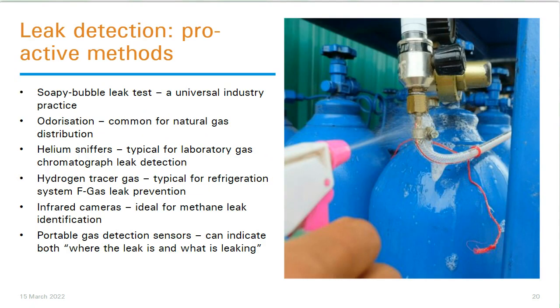What about proactive methods of identifying leaks? These are the kinds of things that you can do during a safety walk or during a regular routine maintenance operation. We can go out with a soapy bubble leak test, a universal practice, and check for leaks. Or we can use infrared cameras to look for IR-specific molecules such as methane. Or we can walk around the site with a portable gas detector, and if it's a multi-gas detector, it can perhaps tell us, number 1, if there's a leak, and number 2, which particular gas is leaking. So there are a number of appropriate techniques that we can use proactively to track down leaks and fix them before they cause a problem.